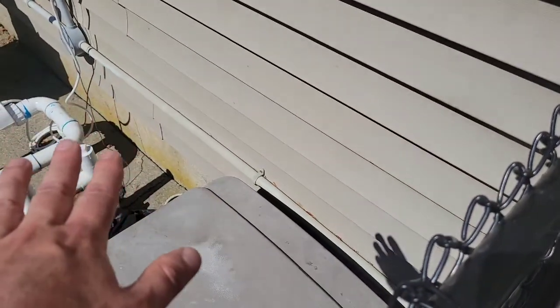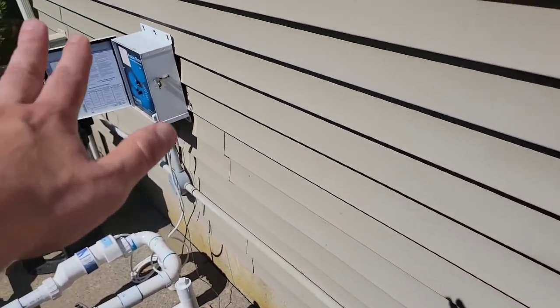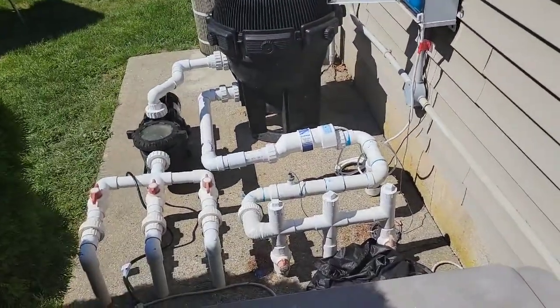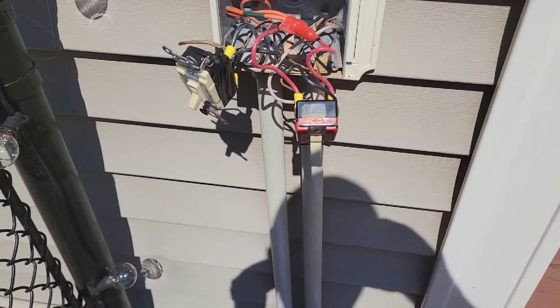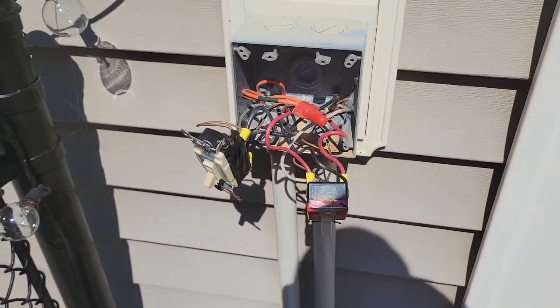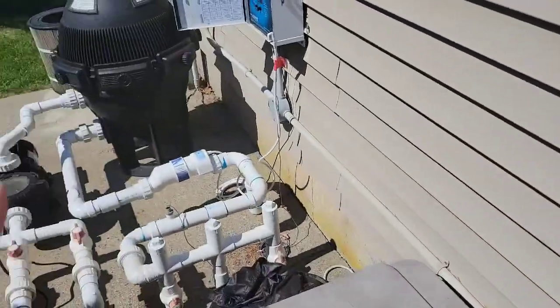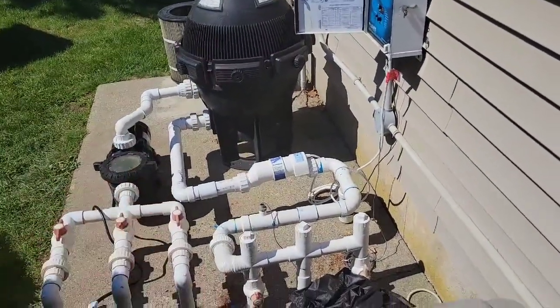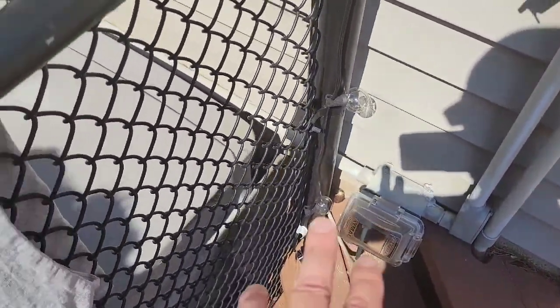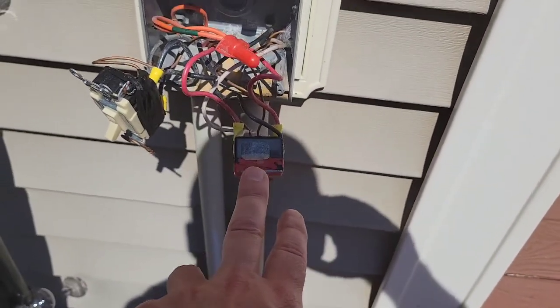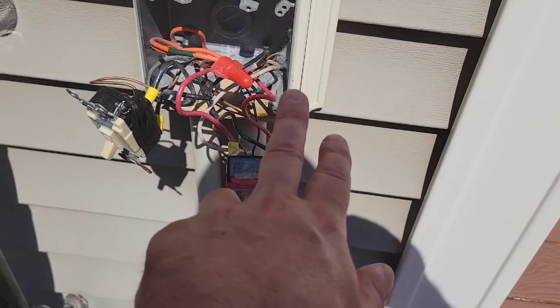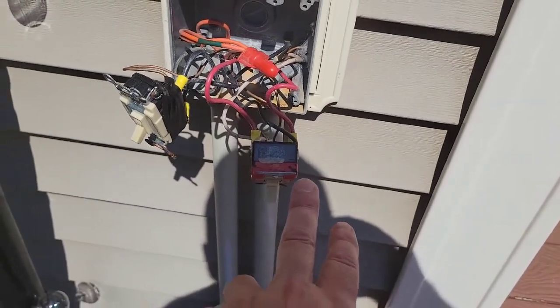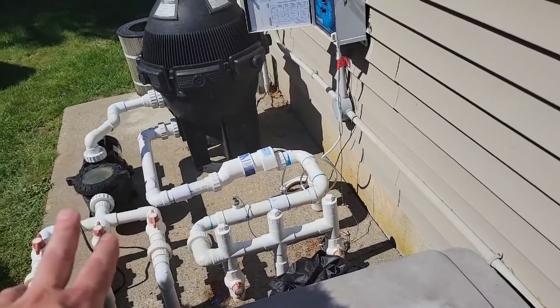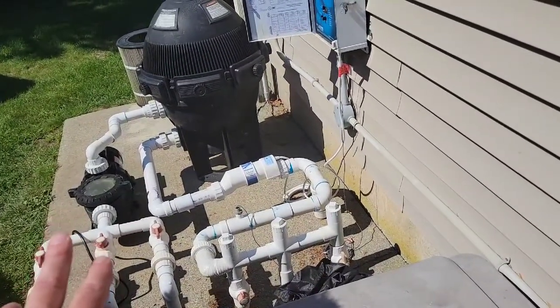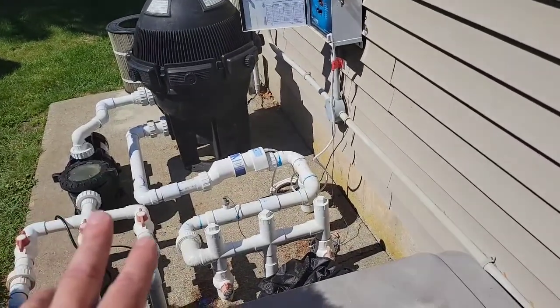Went through the junction box, no voltage. Went to the motor connection, no voltage. Now, we decided to go down to the breaker box and check for a bad breaker, but before I show you that, my original assumption that this was all 120 volts was wrong, and that motor, even though it's running off 120 volts now, temporarily directly through this receptacle box, is good. What we ended up finding out was this is a 220 volt switch that is fed by a different breaker all its own in the breaker box. So that motor needs to be switched back to the 220 volt setting. It's running fine now at 115, but let's go down to the breaker box and we'll show you what happened.